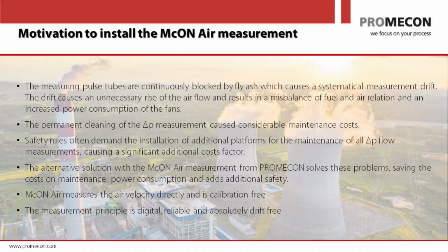So summing up why our measurement brings you significant advantages: it's digital. It will never fail on you in drift, never, over the whole lifetime of the system. It measures the airflow in a direction. So it does not measure some airflow or some wind around the sensors. It measures where the air is going and at which velocity it is going in that direction. Whether the air is spinning or whether the air has a lateral component, it doesn't matter. The big advantage over the current measurement that you have is, of course, that we do not need any analog signals or anything that can affect our measurement. And the output of our measurement is strictly linear. So you don't have to worry about the low end or the high end. Within the measurement range that we give you, our measurement will be correct.